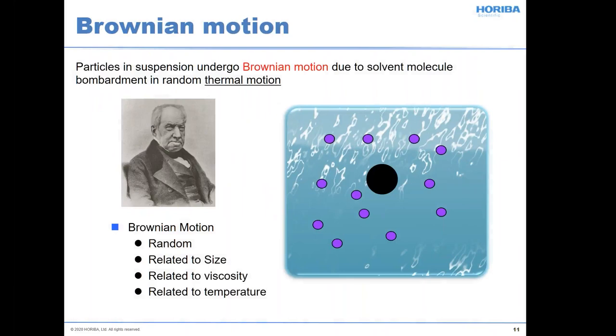The technology really relies on Brownian motion — the random motion of particles due to thermal motion. It's related to particle size, liquid viscosity, and temperature. Generally, people will measure the motion, knowing viscosity and temperature, and from that extract the particle size. It's important to keep this in mind because it helps you interpret experimental results and understand what you can and can't do with these sorts of techniques.